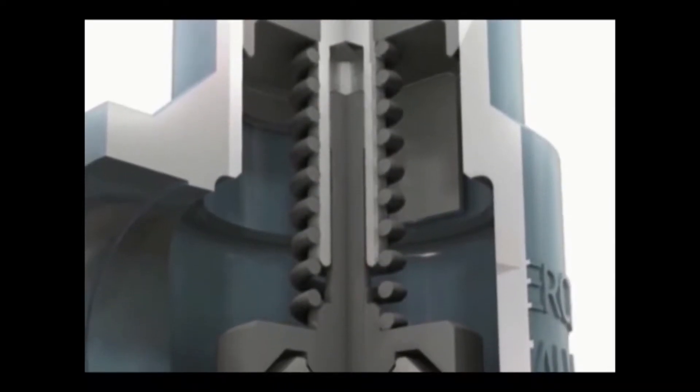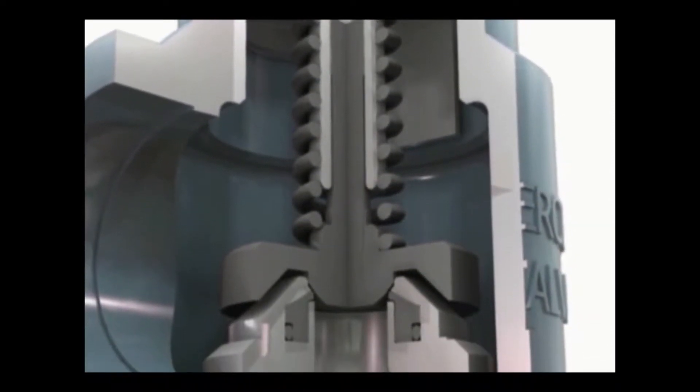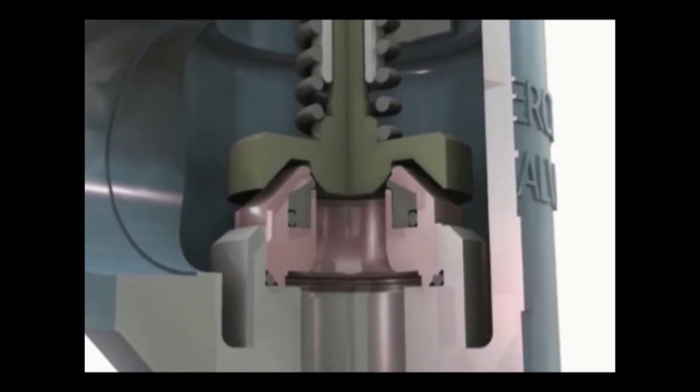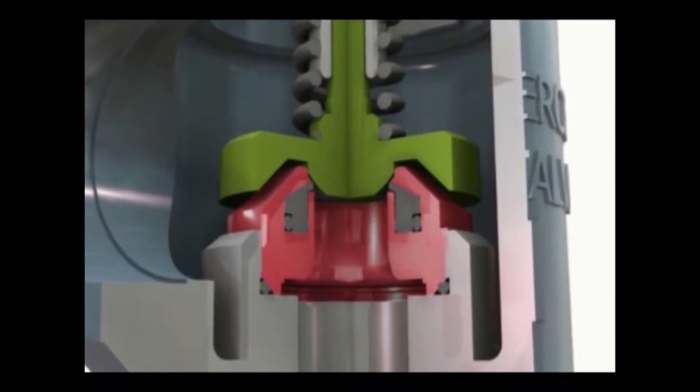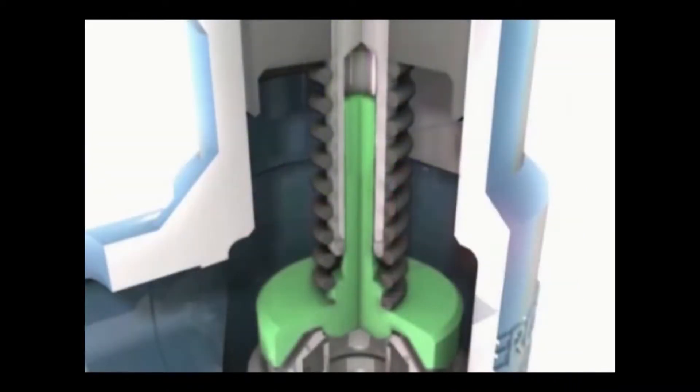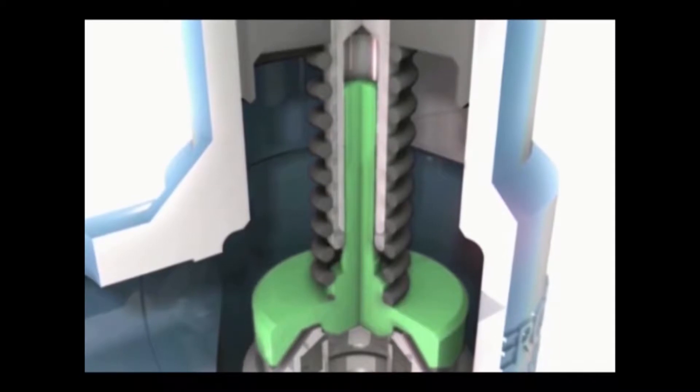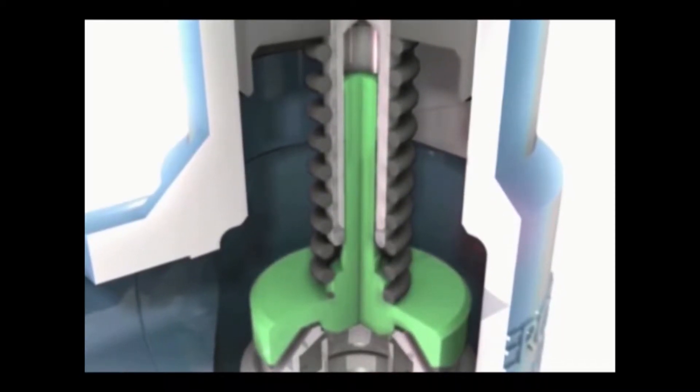With Auto-Seat Technology, the fully guided disc aligns the disc with the nozzle to allow the disc to open, close, and seat and seal each and every actuation. The disc stem is guided through the center of the adjustment screw and the bottom of the disc is radius to align with the nozzle.